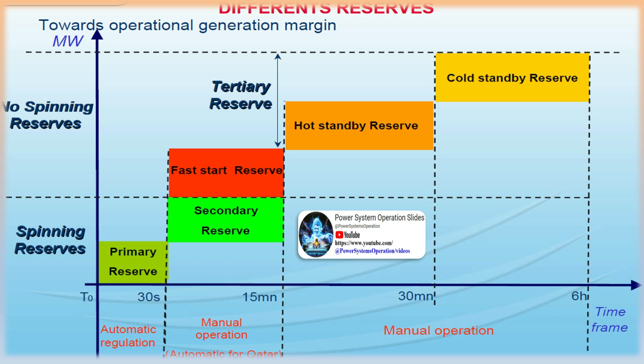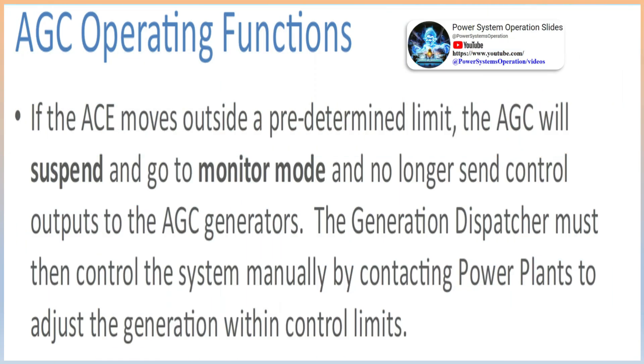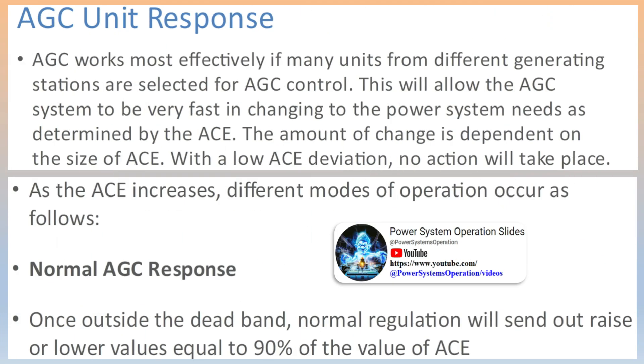Common AGC operation: having many generating stations respond to ACE load changes could also benefit the transmission system by not moving all generation changes from one location and possibly causing a transmission system overload. If the ACE is allowed to go outside the setting limits for automatic control, the AGC system will suspend and no control signals will be sent to the units. The generation dispatcher will only be able to monitor the system with no automatic actions occurring. Manual actions by the generation dispatcher will be required. The problem must be corrected manually by adjusting generation or changing schedules to bring the ACE within limits for automatic control. The generation dispatcher must not under any circumstances individually adjust schedules to bring AGC within control settings, as this action could have a negative impact on the power system.